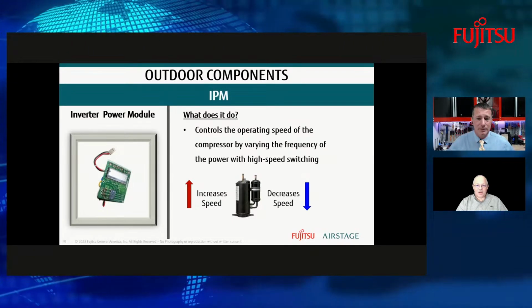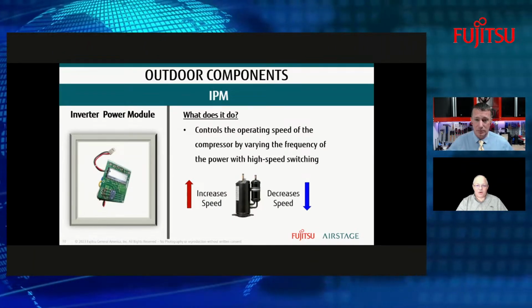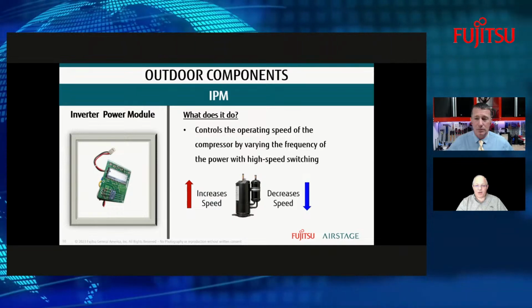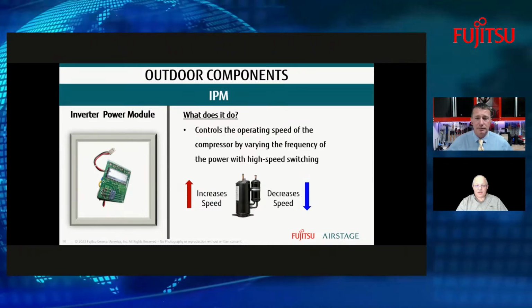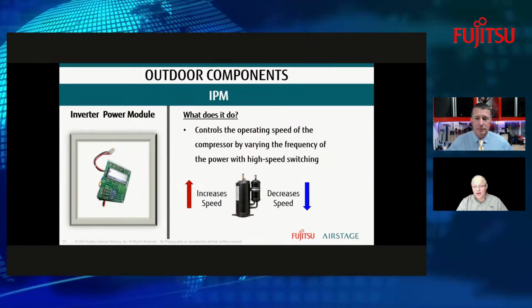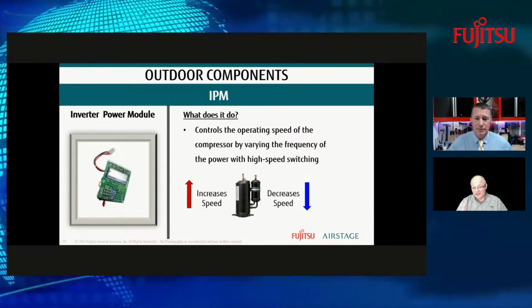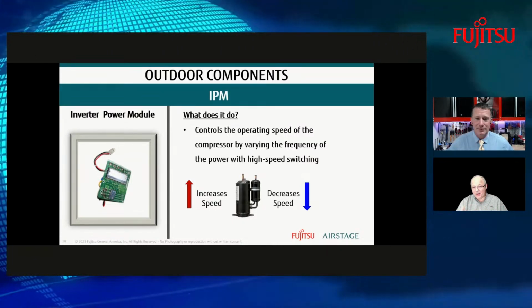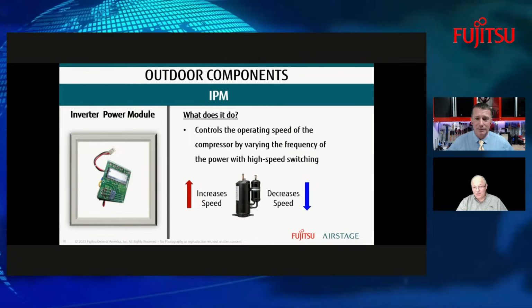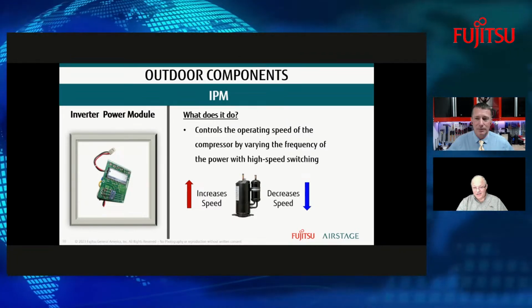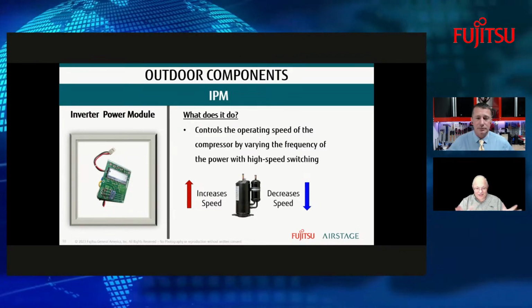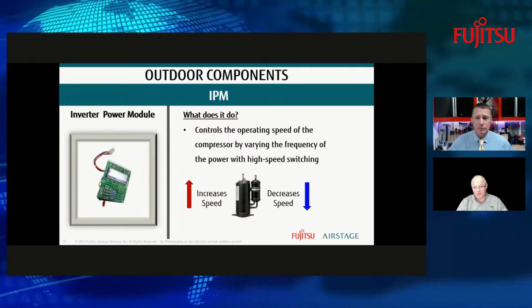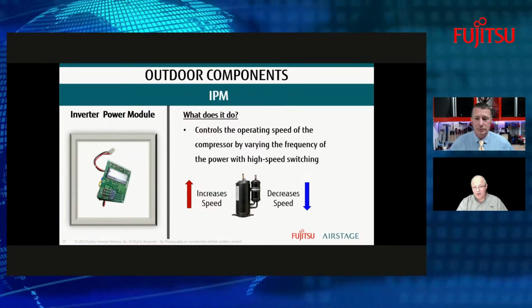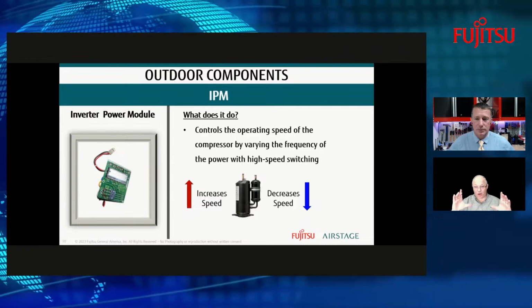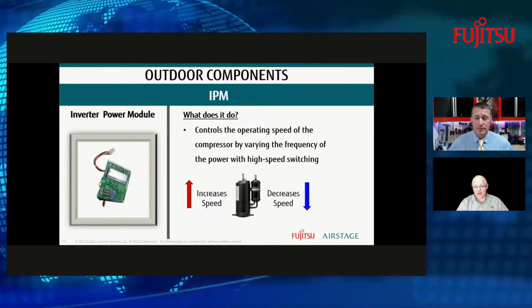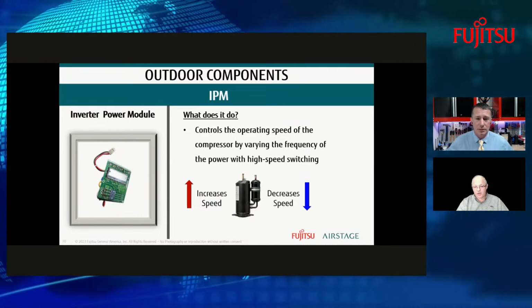All right, so let's talk about the IPM. This is a term that we use. It's called the inverter power module. Right. Now, this is the little board. I know what this is because it's a smaller board, so I know it goes to a single-headed system. It's not a multi-zone. If it was a multi-zone, then you would have a power inverter module built into a big, large board. All in one component? So this is for the smaller single-zone systems.